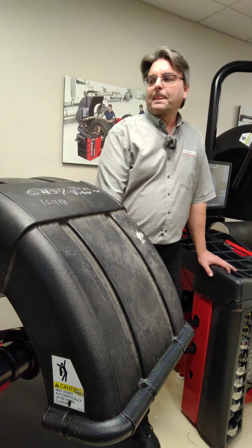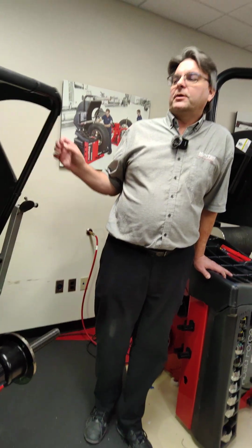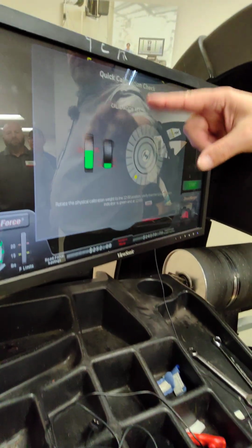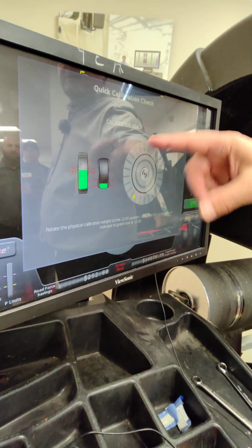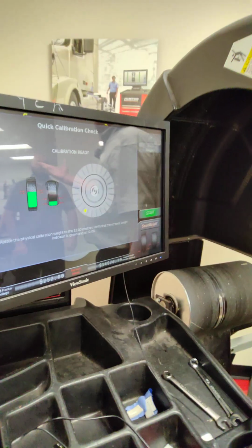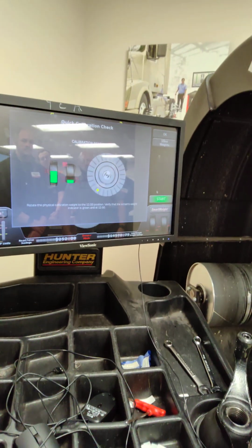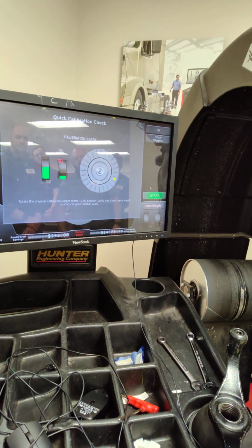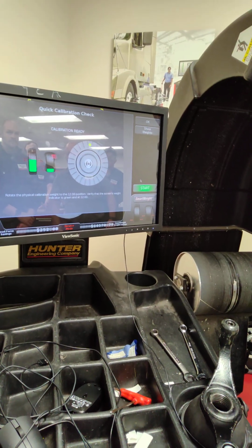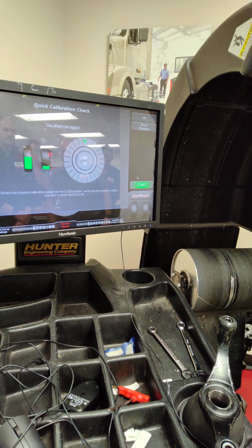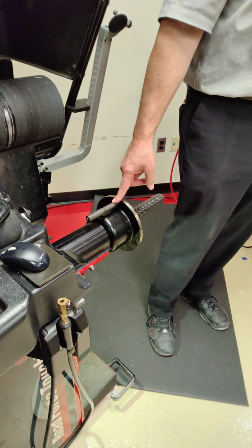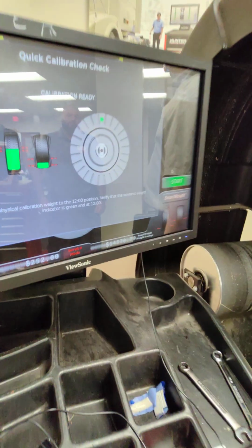All right. So 2 things happen here. The one thing is you see the green over here, and it either says calibration ready in green, or it's going to say calibration required, and it's in the red. So as long as it says calibration ready in the green, everything's great. The second thing we're doing is making sure that it knows where top dead center is. So when you put the weight at top dead center, the little yellow light should turn green, okay?